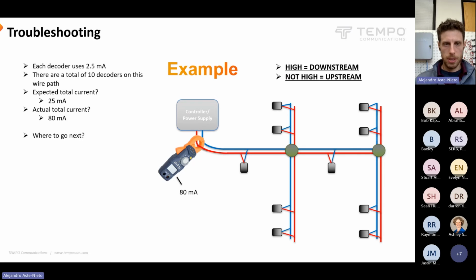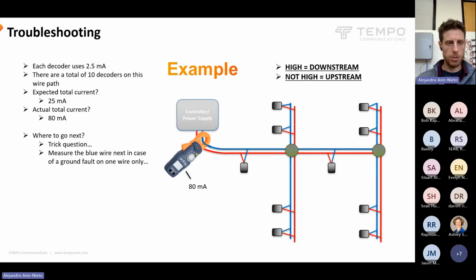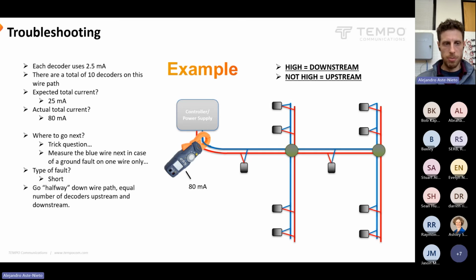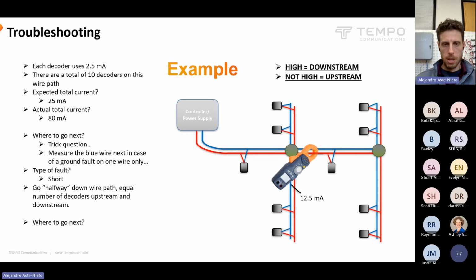That indicates that the problem is downstream. Obviously, we're upstream of everything. So you would think go downstream, but this is kind of a trick question. We have to make sure we measure both wires before we make any conclusions. So measure red and blue in case there was a ground fault on just the red wire. But here we have 80 milliamps on both wires. So that indicates we have a short. We have high current on both wires. That's a short. So from here, we'll go halfway down the wire path to where there's equal numbers of decoders upstream and downstream. So where is that? It's about right there. We have 5 decoders downstream here, and we're seeing a normal number, 5 times 2.5.